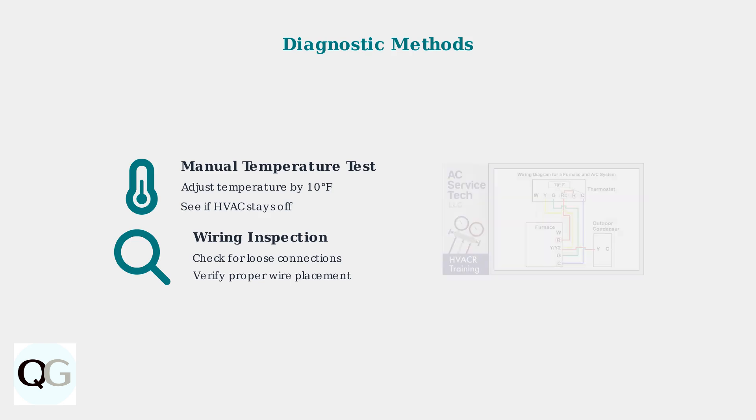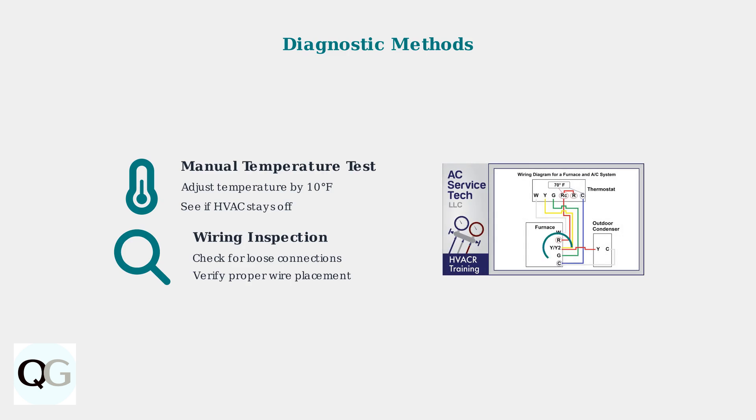Inspecting the thermostat wiring for loose connections or improper placement can reveal communication problems between the thermostat and your HVAC system. This wiring diagram shows the proper connections between your thermostat and HVAC system. Pay special attention to the C-wire connection, which provides continuous power to prevent short cycling issues.